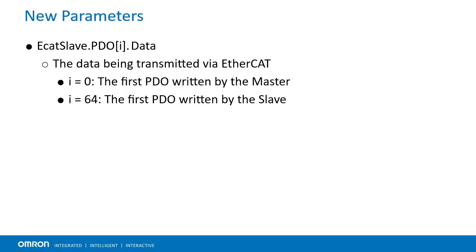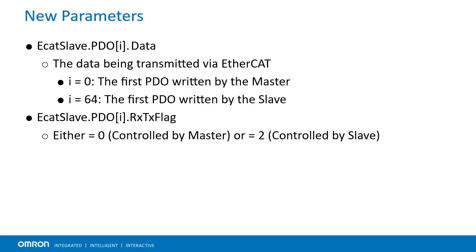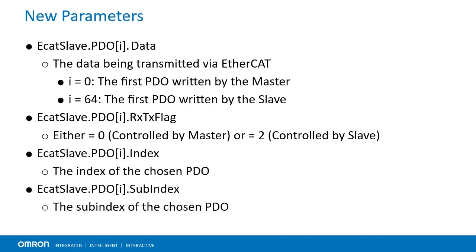This can be confirmed by checking ECATSlave.PDO[i].rxtx_flag. If this parameter is 0, write protection is enabled and PMAC can only receive data in that register — the user cannot write to it. If this parameter is 2, the user can write to this value and the master will receive the value written. Users can also check ECATSlave.PDO[i].index and ECATSlave.PDO[i].subindex to see where the data will be stored and where the master device will read it.